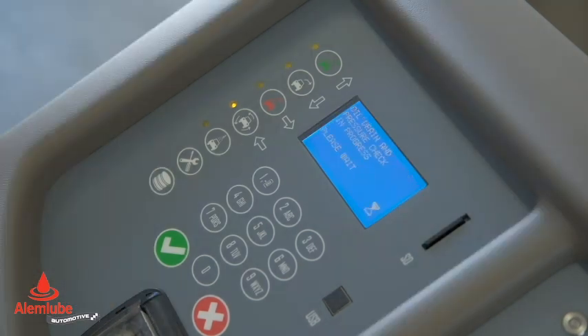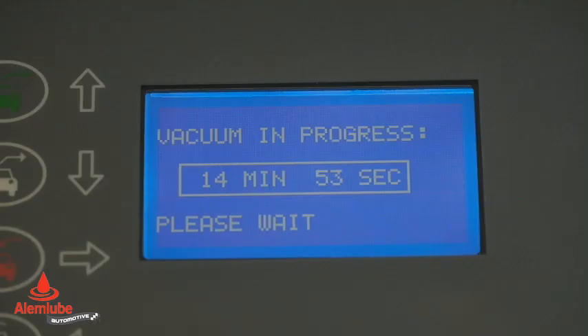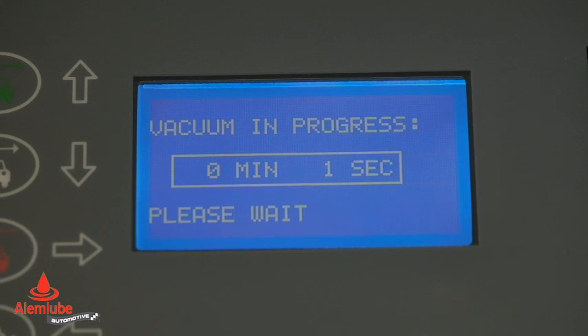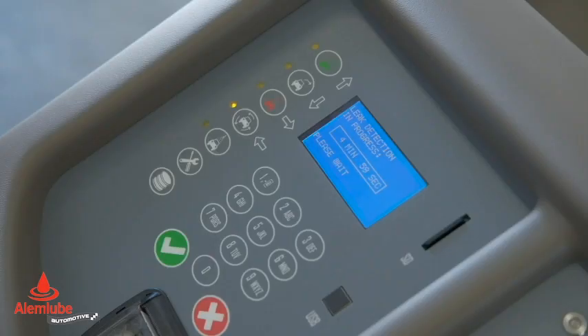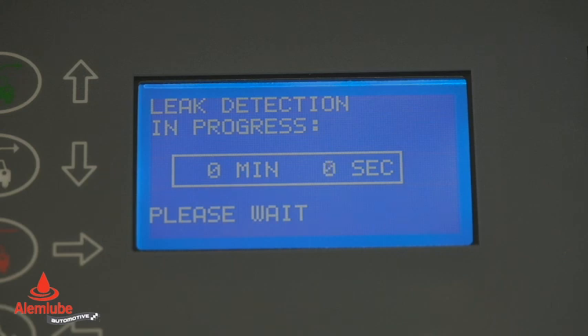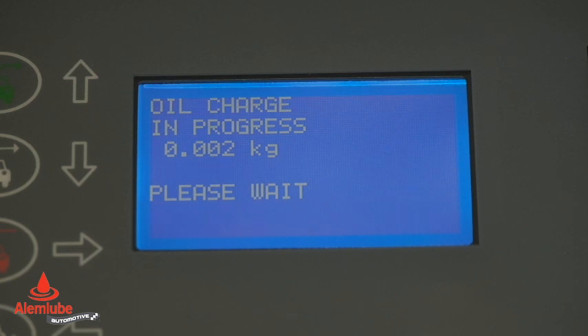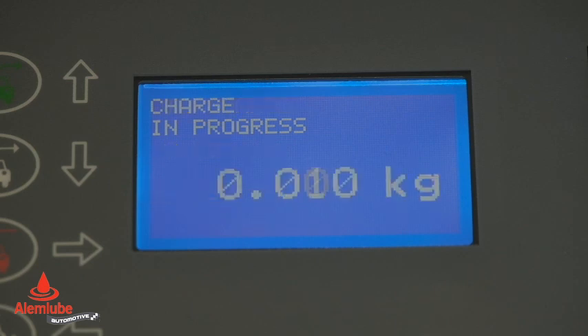Now the gas recovery phase has ended and the separated oil discharge phase begins. Once the oil discharge phase is over, the vacuum phase begins. In this phase, the residual moisture is extracted from the air conditioning system. Now the vacuum phase is finished and the test phase in search of leaks begins. In this phase, a possible rise in pressure is checked. After the vacuum and test phases, the oil, tracer and gas charge phase begins inside the system.